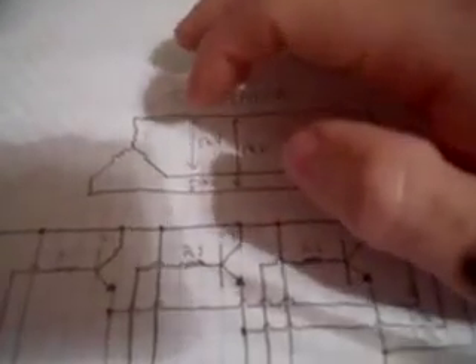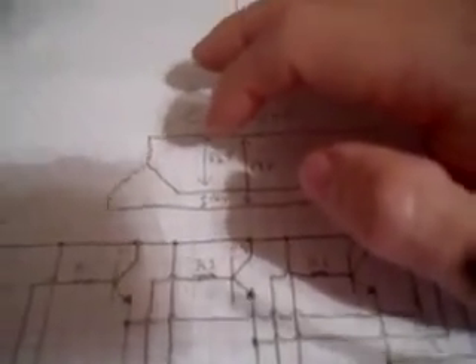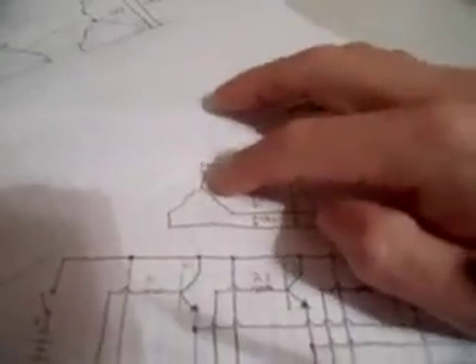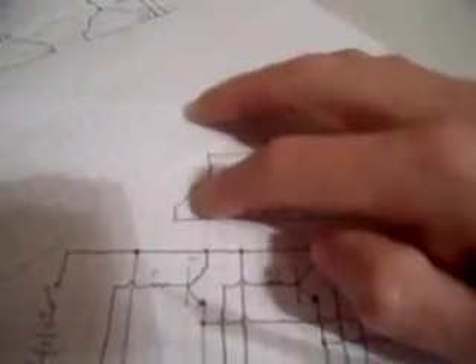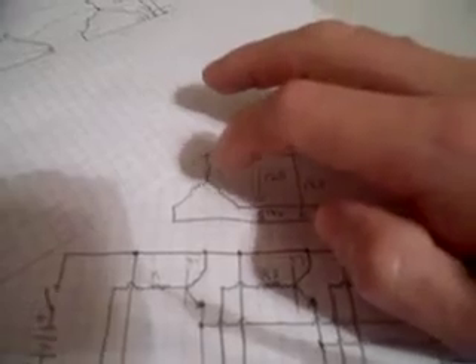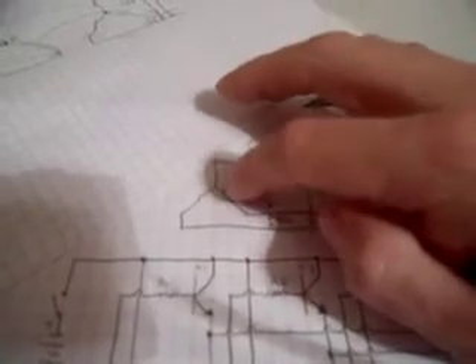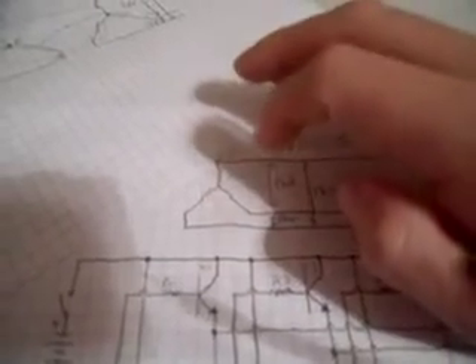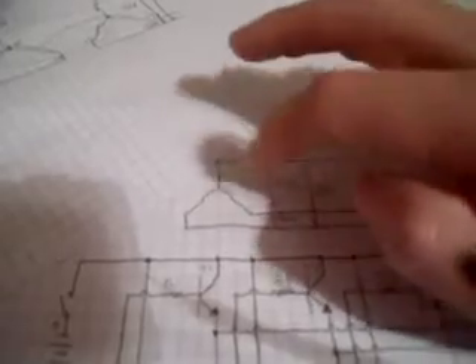So here's what's going on. I have L1, L2, and L3 coming up to a bank of 3 transformers. There's one transformer here, one transformer here, one transformer here. One end of the transformer is connected in a central connection like this, and the other ends of the transformers go to L1, L2, and L3. But we're going to take it up another notch and go all the way up to 240.